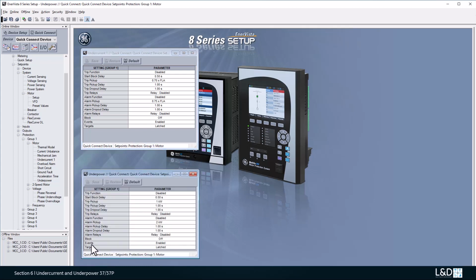The underpower element responds to the total three-phase real power measured from the phase current and voltage. Underpower may be used to detect loss of load condition. The loss of load condition does not always cause significant loss of current. Power is a more accurate representation of loading and may be used for more sensitive detection of load loss or pump cavitation.